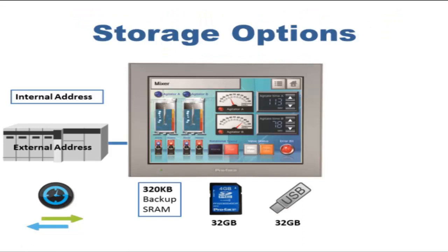Data is stored in either the local battery-backed SRAM memory or in an external memory device. The internal memory size is model dependent, ranging up to 320 KB. This equates to 316 samples of 512 word values or 81,000 samples of one word value. Many GP4000 terminals support SD and SDHC memory cards up to 32 GB. Every GP4000 terminal supports USB memory devices also up to 32 GB.